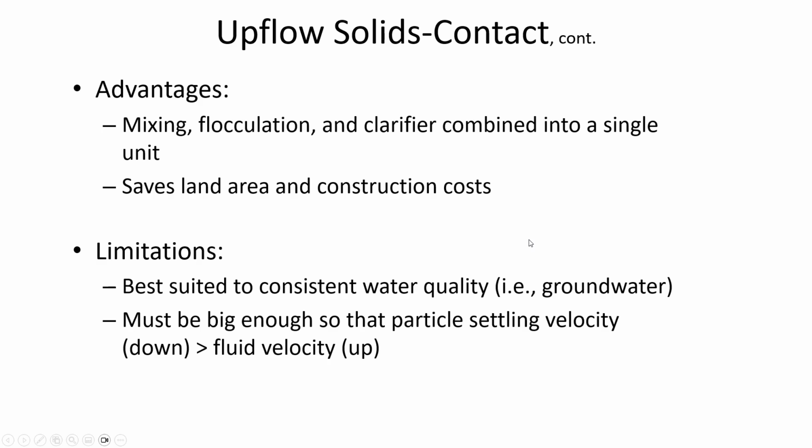Surface water might be okay if we were taking from maybe a high altitude lake where we don't expect a lot of changes in the temperature and the turbidity and the nutrient content over time. And then the other limitation is that we have to size these upflow solids contact chambers so that the particle settling velocity that you'd expect is greater than the fluid velocity that's up.